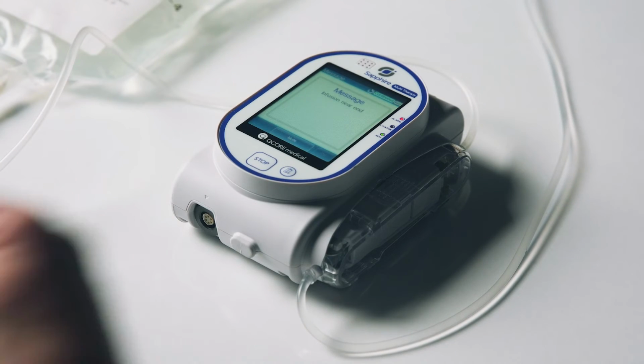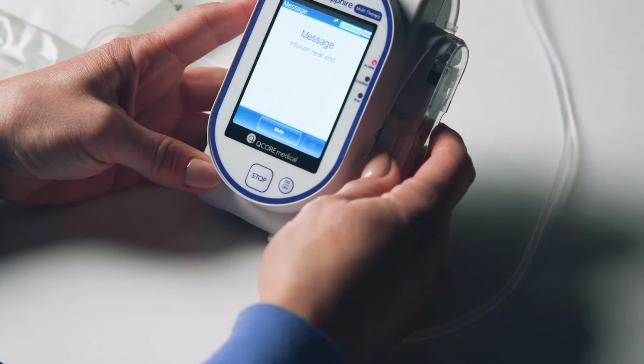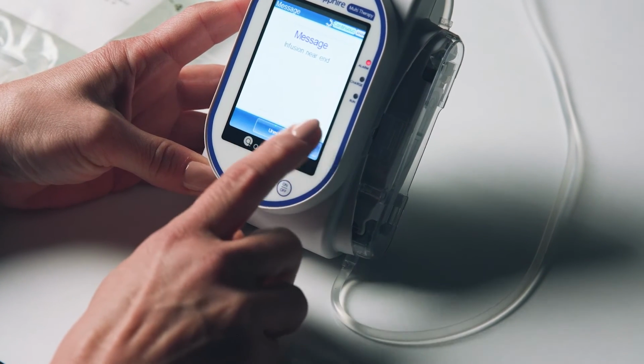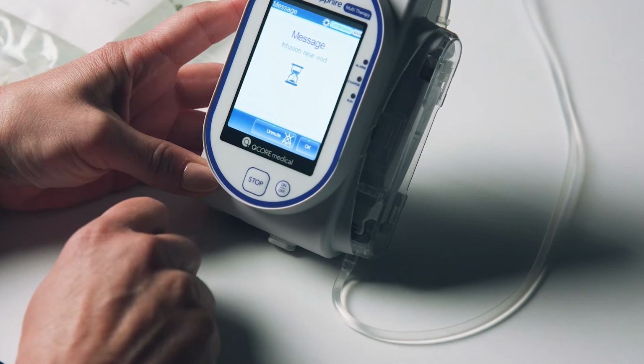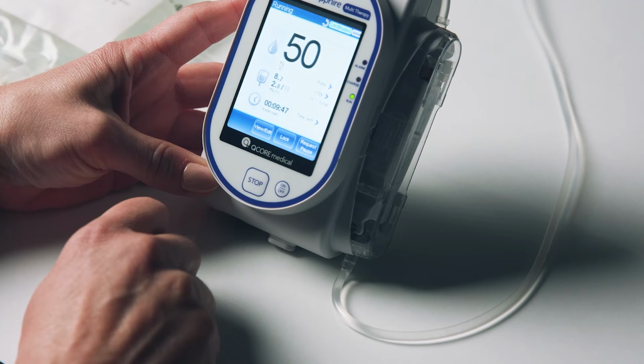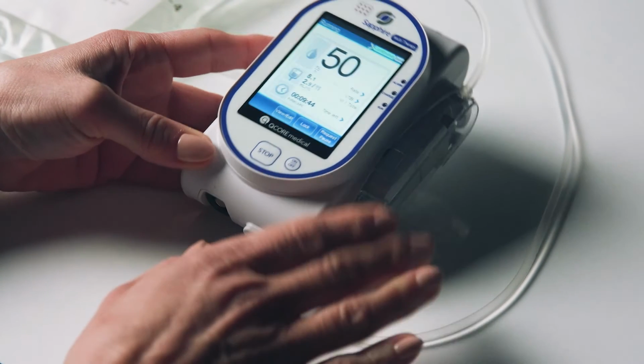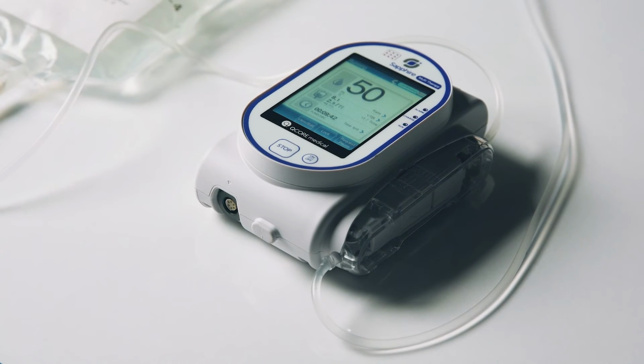Should an alarm display during your infusion, you must press Mute at the bottom of the screen before clearing the alarm. After the cause of the alarm is corrected, press OK to dismiss it. Then press Request Continue, followed by OK to resume your infusion.